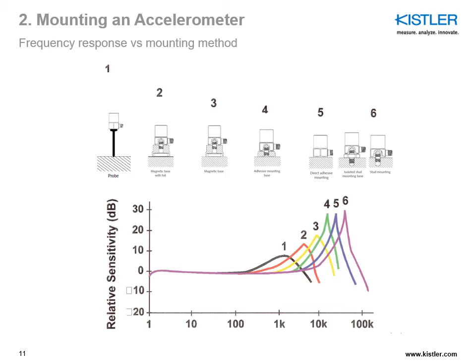Here is a summary of what we just discussed. From left to right, we have the softer mounting to the stiffest mounting. Whenever we calibrate a sensor that can be stud mounted, we always use stud mounting — that's mounting type number six (purple line) — giving the best frequency response. If you use an isolated stud with an integral plate between sensor and mounting surface, that's between five and six, and the resonance peak is fairly close to stud mounting, just a little lower because of the additional plate acting as a mechanical filter.